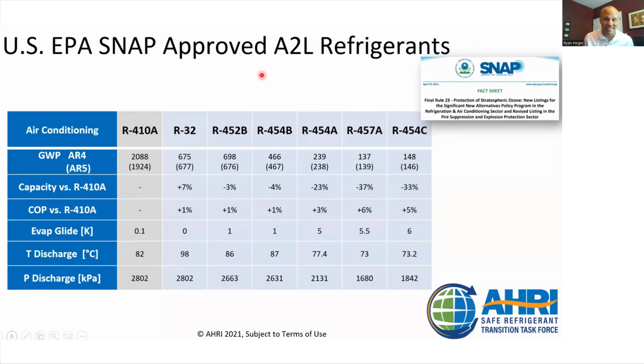So R22 is not a blend. R32 is not a blend. But 410A, 407C, 454B, those are all blended refrigerants, more than one thing mixed together. If you have two refrigerants mixed together, those two things do not likely have the same boiling point. So they're going to evaporate off at different temperatures in the evaporator coil. The glide is the difference in temperature at which they are going to evaporate off.